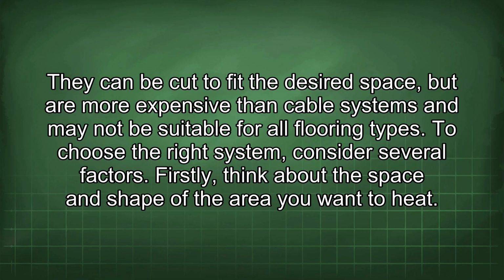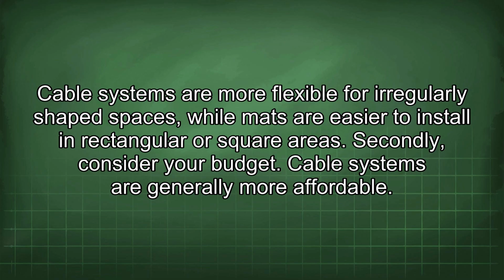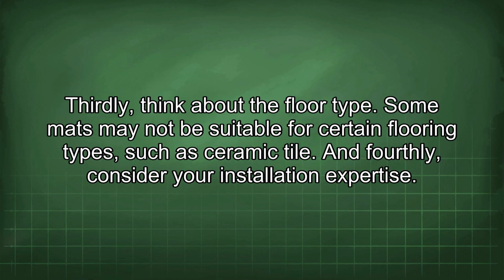To choose the right system, consider several factors. Firstly, think about the space and shape of the area you want to heat. Cable systems are more flexible for irregularly shaped spaces, while mats are easier to install in rectangular or square areas. Secondly, consider your budget. Cable systems are generally more affordable. Thirdly, think about the floor type. Some mats may not be suitable for certain flooring types, such as ceramic tile.